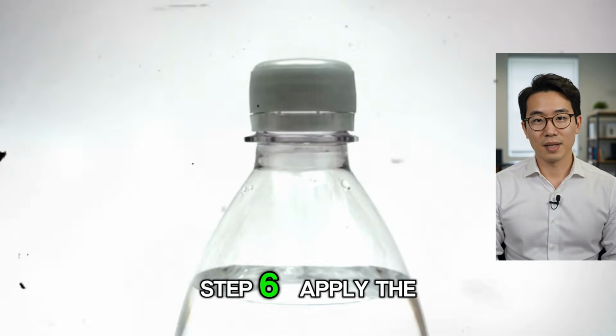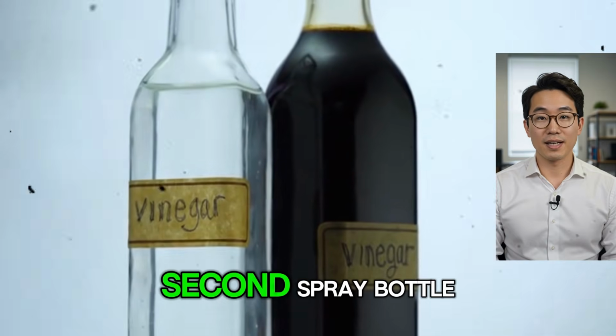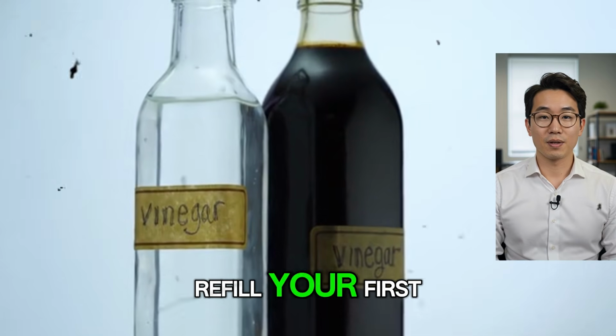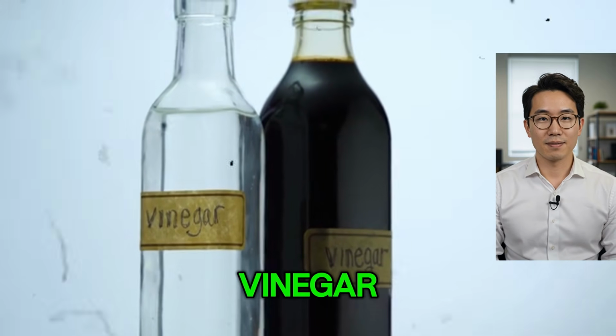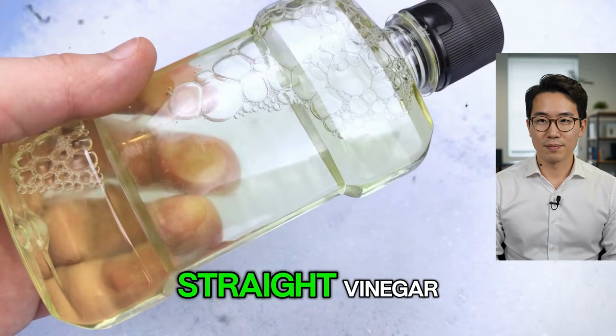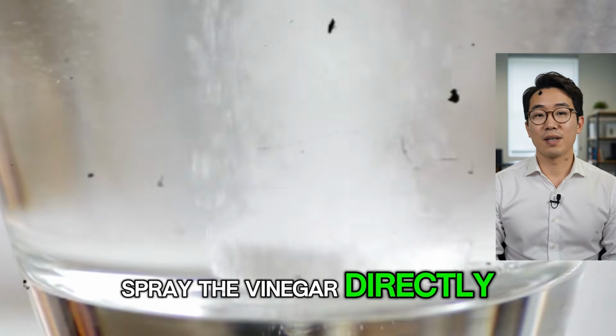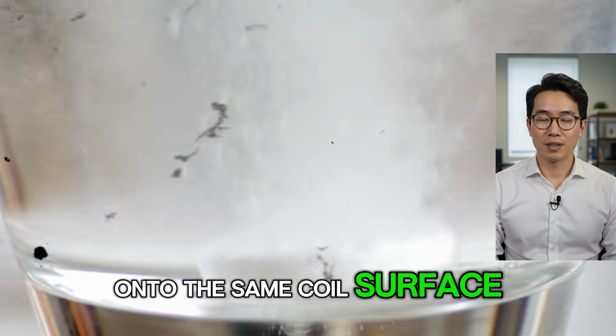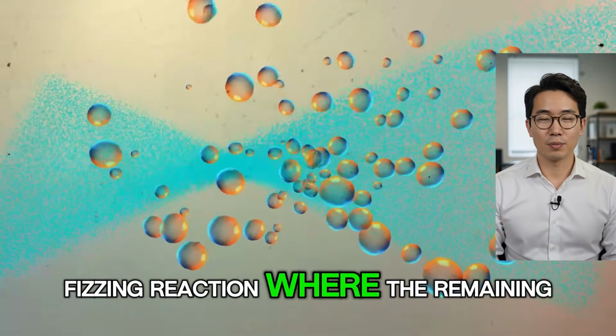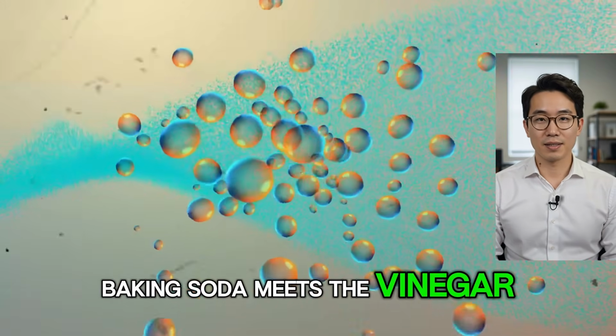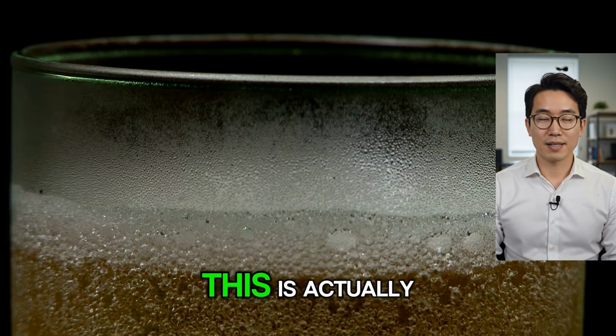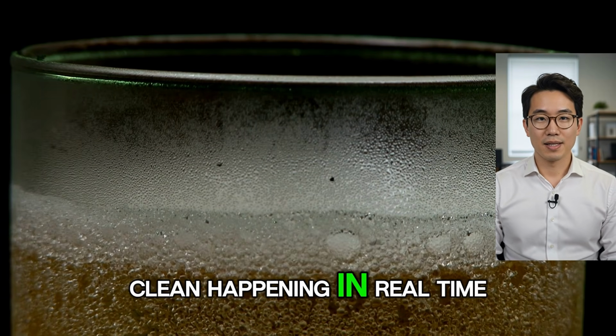Step 6. Apply the white vinegar. Now fill your second spray bottle, or rinse and refill your first, with plain white vinegar. No dilution needed for this step. Straight vinegar. Spray the vinegar directly onto the same coil surface. You will hear and see a light fizzing reaction where the remaining baking soda meets the vinegar. This is completely normal. This is actually the second stage of the clean happening in real time.